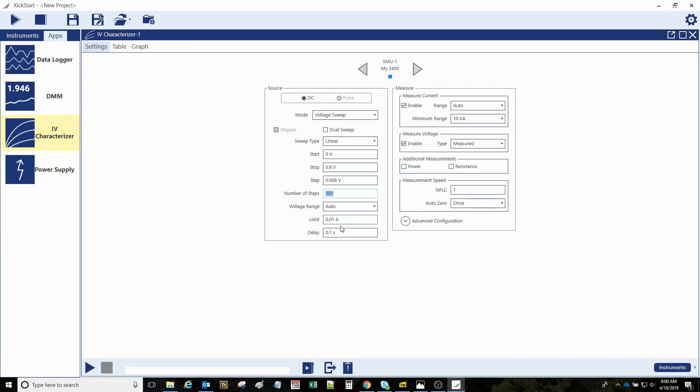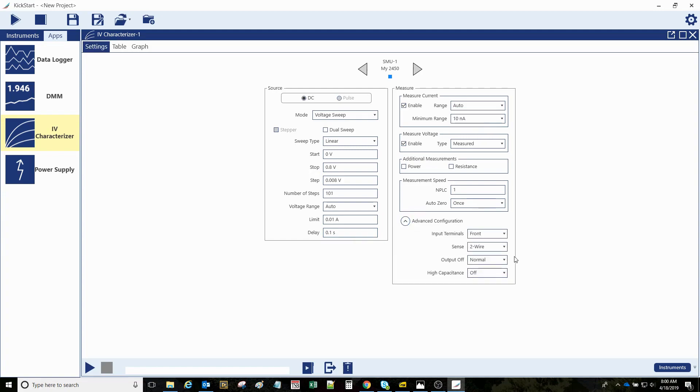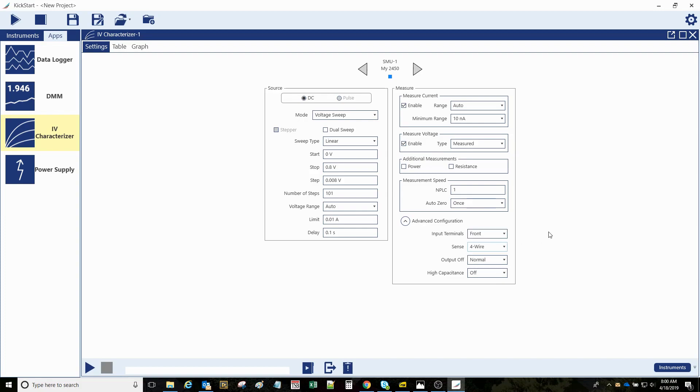I'm going to accept most of the defaults here, including this delay time. Under advanced, though, I want to indicate here four-wire connections through the front panel terminals of the instrument. Okay, I think we're ready to go.